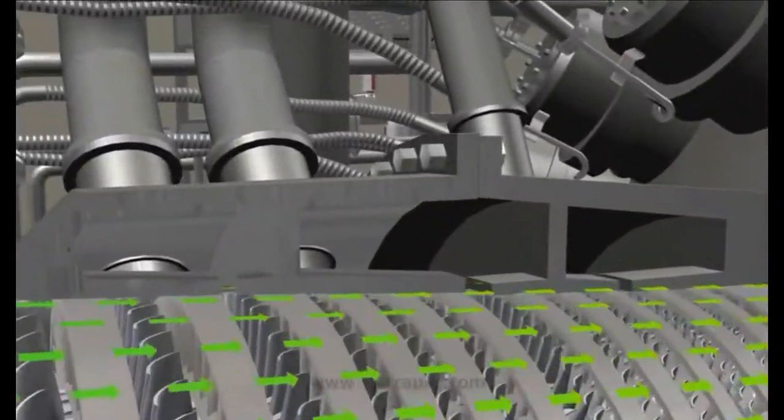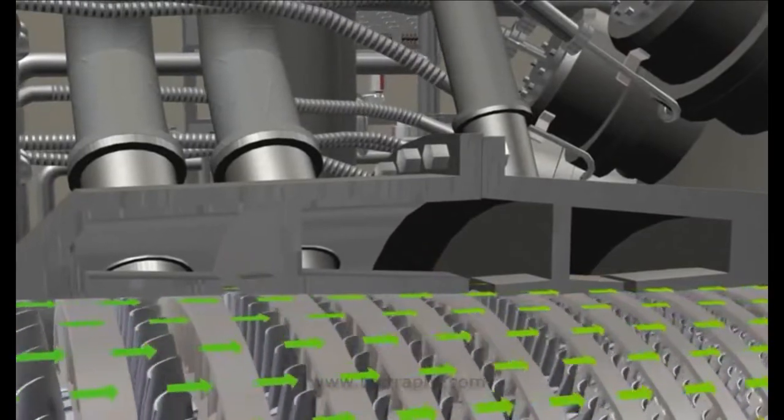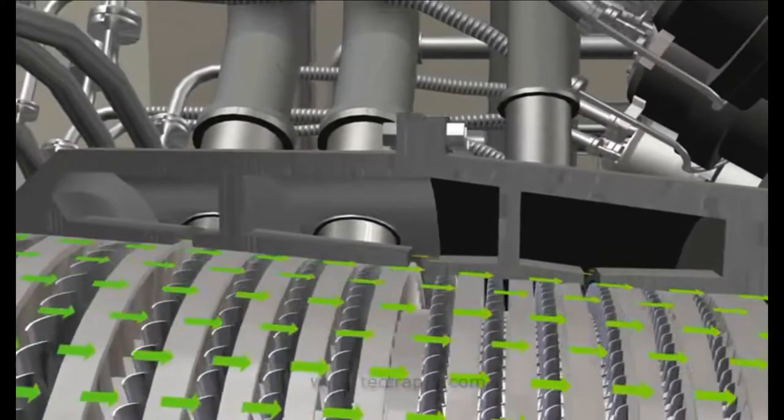To manage the air flowing into the compressor for surge prevention and to provide cooling air flow to turbine stationary vanes during normal operation.